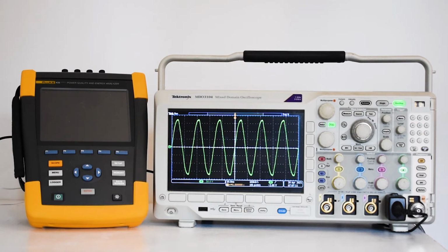To illustrate, we'll display a utility waveform in the Tektronix mixed domain oscilloscope, taking care not to connect the probe ground return lead to the side of the line that is referenced to, but floats above, ground potential. Then we switch on the channel and press auto set to get a stable display. There are no obvious harmonics, but it is not a very pure sine wave, lots of noise today.